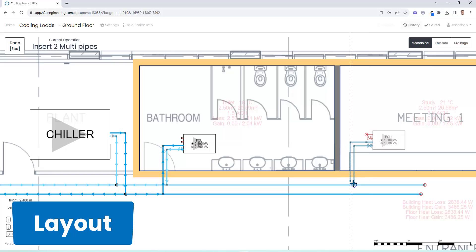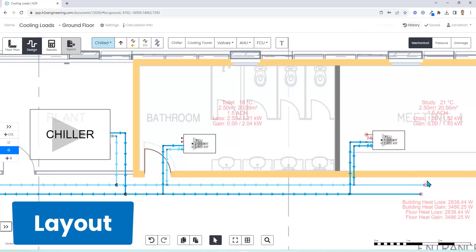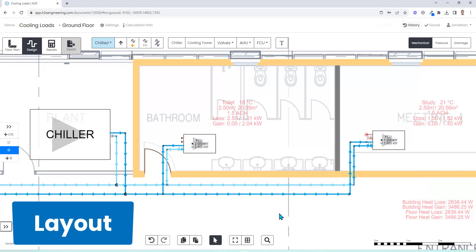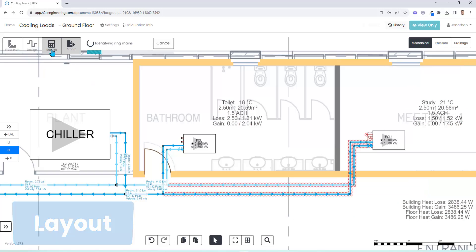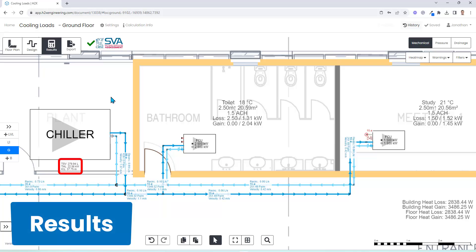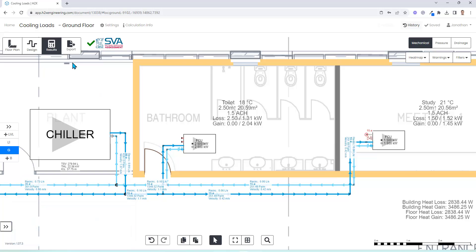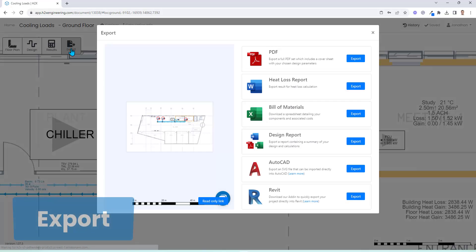Then in a matter of seconds, you can view your results which combines your layout on all the technical properties and parameters you have. And it provides a range of information like your total system volume, the total kilowatt load, the index circuit length, and every pipe is sized with the flow rates, velocities, and pressure drops per meter provided.